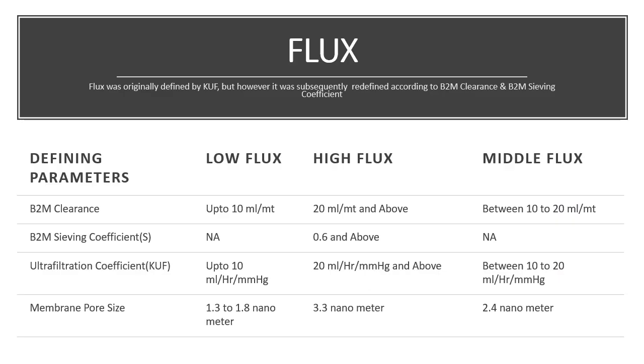The next dialyzer characteristic is flux. Flux was originally defined by KUF, but was subsequently redefined according to beta-2 microglobulin clearance and beta-2 microglobulin sieving coefficient. The defining parameters are: beta-2 microglobulin clearance, beta-2 microglobulin sieving coefficient, ultrafiltration coefficient (KUF), and membrane pore size.